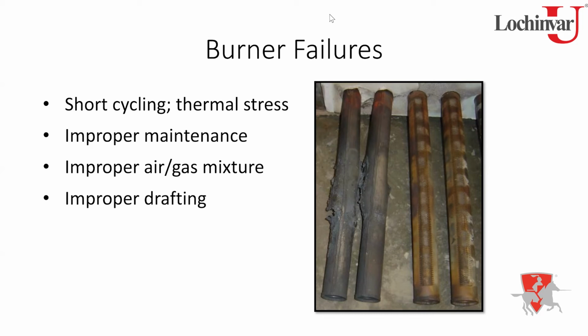If you see a real red, orange flame on an appliance, your CO is probably high enough to kill birds in mid-flight over the stack. So you might want to shut it down and start checking a couple of things. And one thing that I always throw out there, if something's going on with the unit, it's not lighting, terrible flame, something like that, don't just start with adjusting gas valves or air pressures or anything. Start with your cleaning and then set the unit up, and you'll probably be okay. Exactly. So if it's been in for a long time, start with the cleaning first before you start to set air and gas, because if the burners are dirty or the heat exchanger is dirty, it's going to throw all those other numbers off.